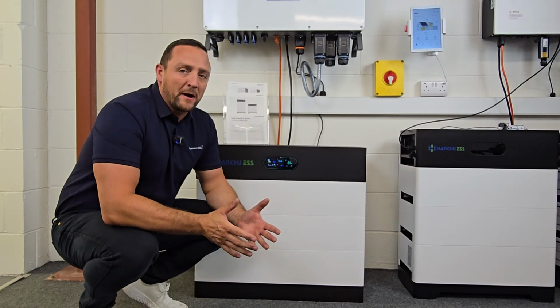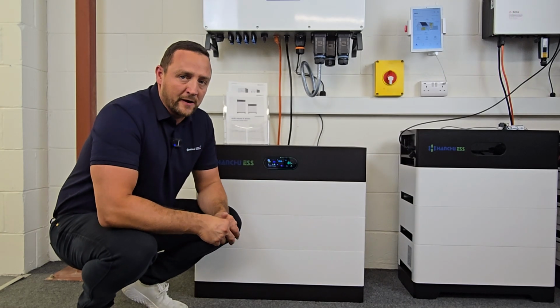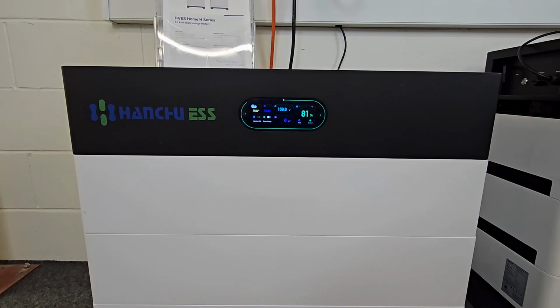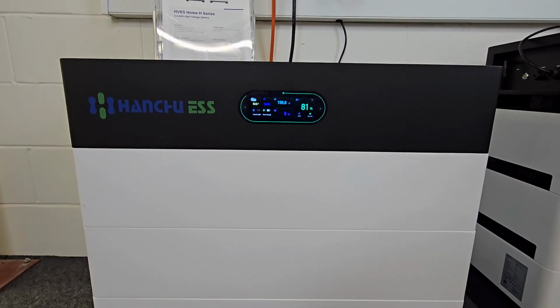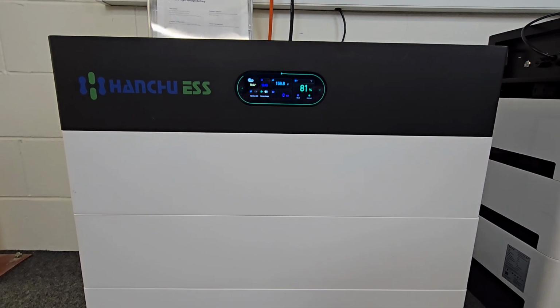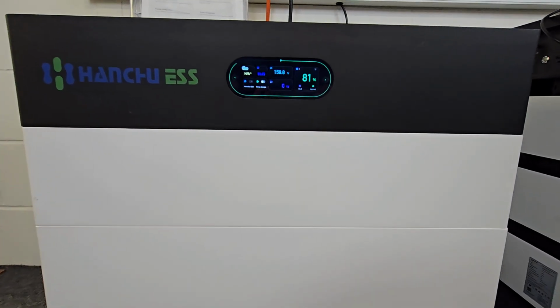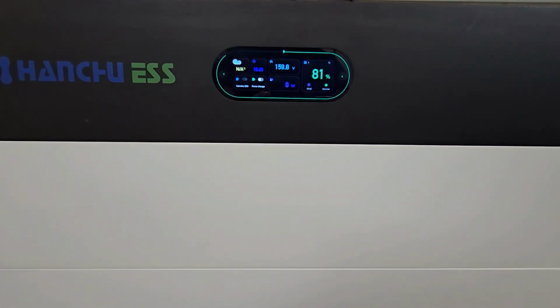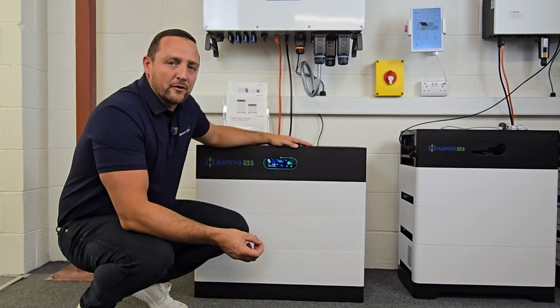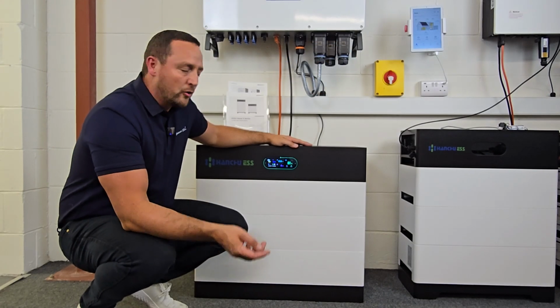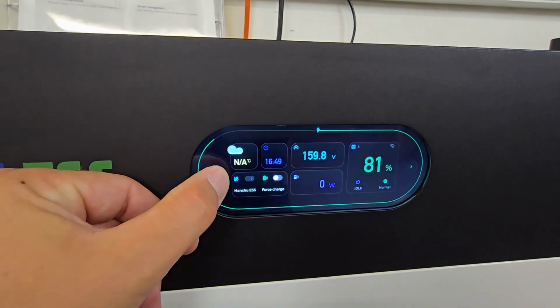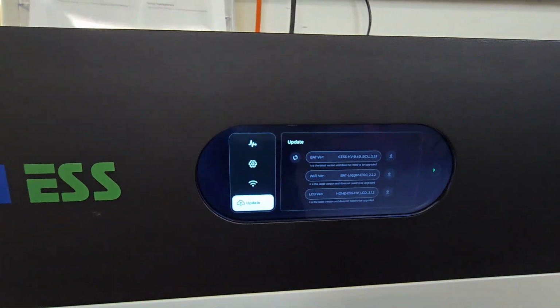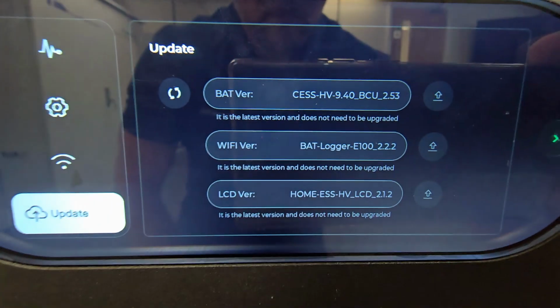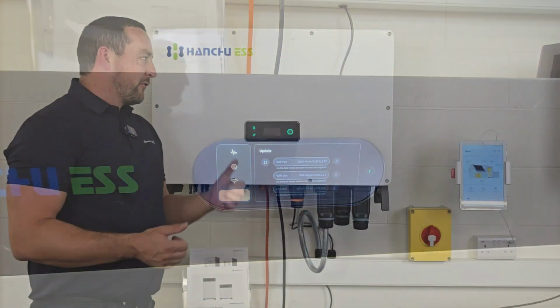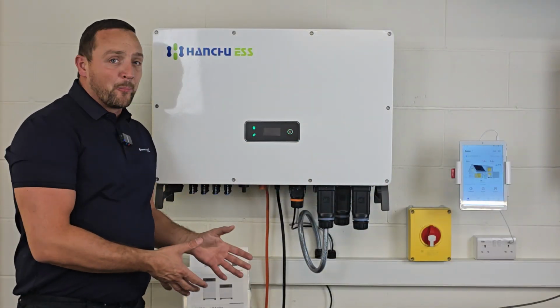So with each battery stack, you do need a BDU for each stack. This is effectively the brains of the system. And with the BDU comes this really good LCD screen. The LCD screen will give you lots of information, including the SoC of the stack. But what's really good as well, as an installer or an end user, you can check for firmware updates via the screen. And just by the push of a button, you can upgrade the firmware of the battery stack. So there you are, there is the HANCHU C&I range and its compatible battery.